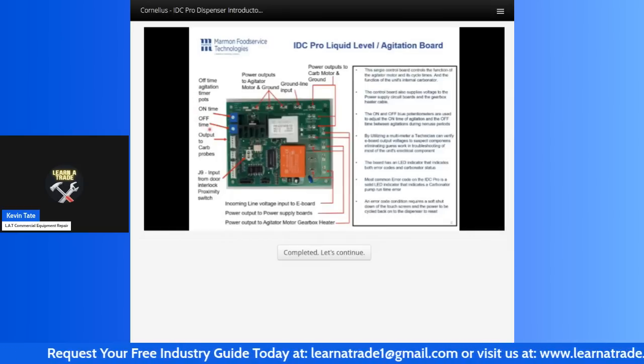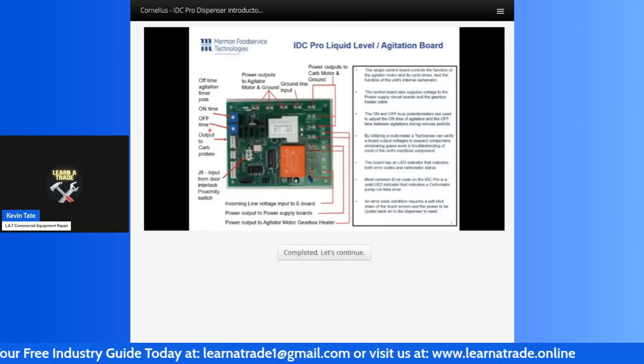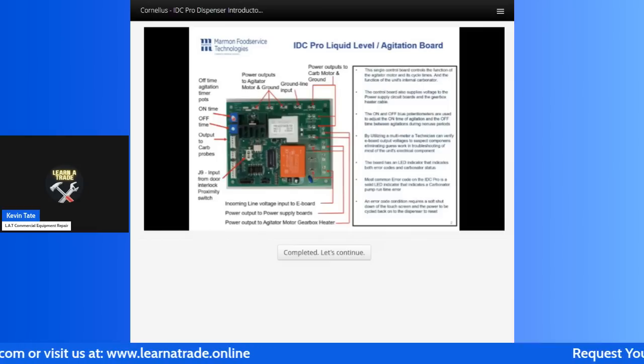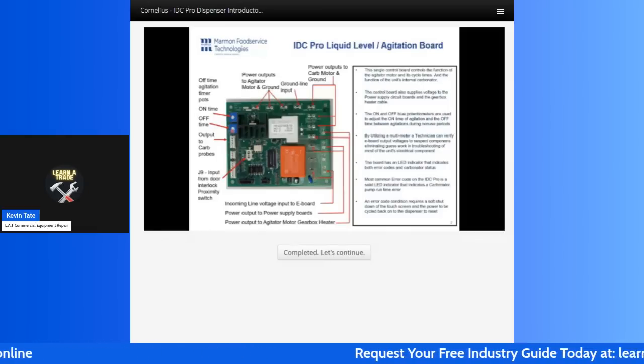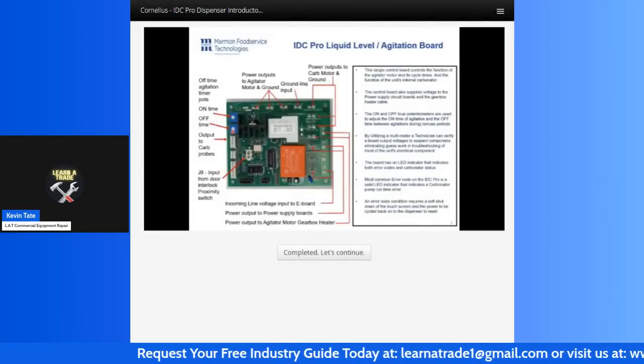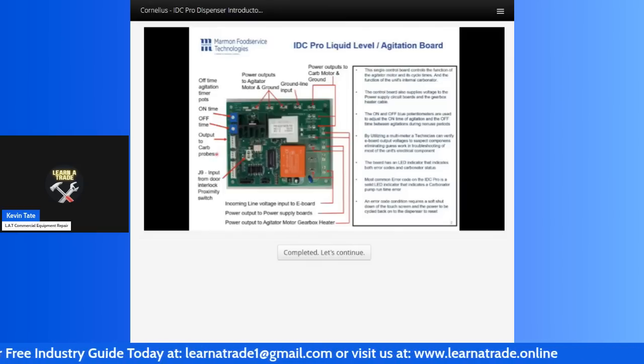On the left side of the board, you'll see the two blue potentiometers. The top one is for the on time. That's how long the motor comes on and runs when it's set for a particular time. Then there's the off time, and that's how much it waits in between before it re-agitates the ice again. And those are adjustable, and we'll talk about that in the next couple of slides.